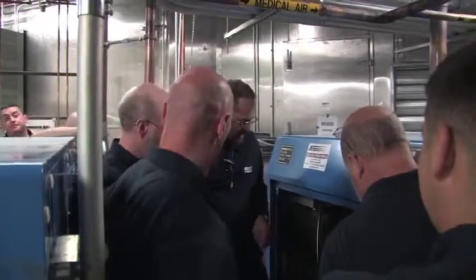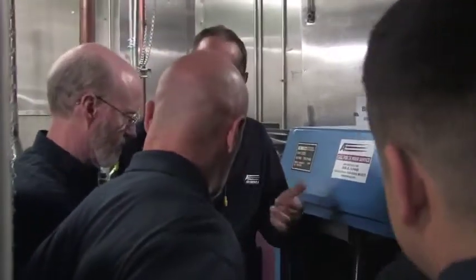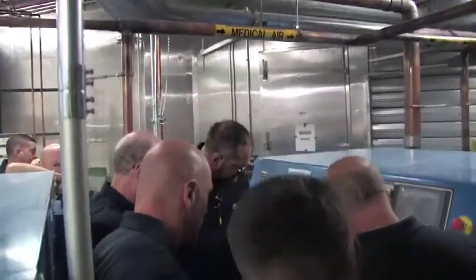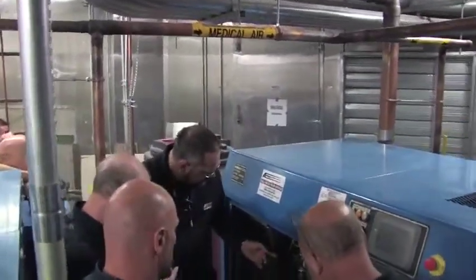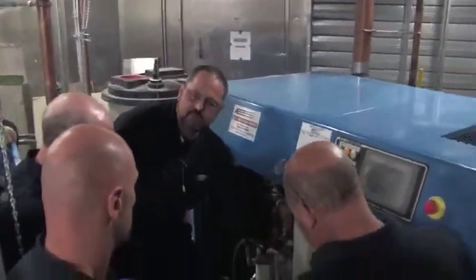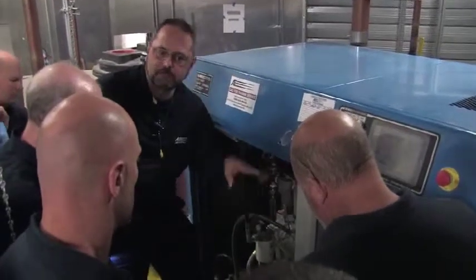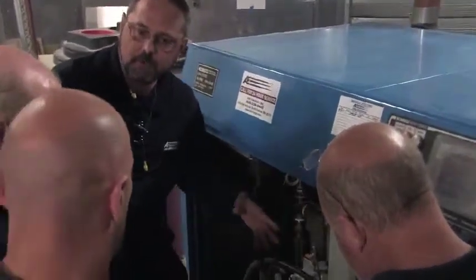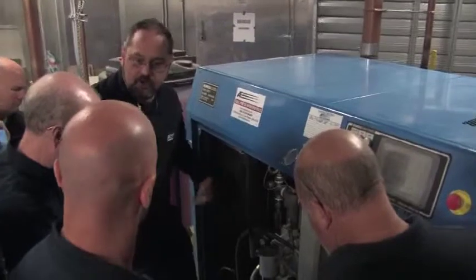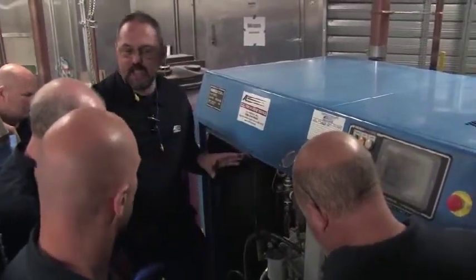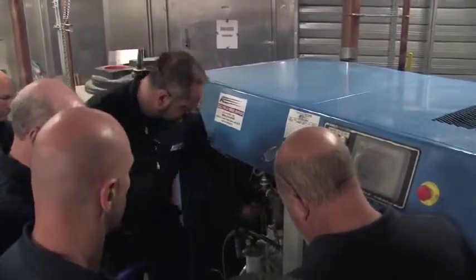It'll shut down instantly, because it's looking for pressure and it's also looking for circulation. But the trick with this is that you can shut the sensor. Basically, we just isolated the pressure sensor that's at the end of this tube. It's still getting oil, it's just not getting the signal. The pump's going to run. You're still going to get oil pressure, so you're not damaging the machine just to test the sensor. Cool.